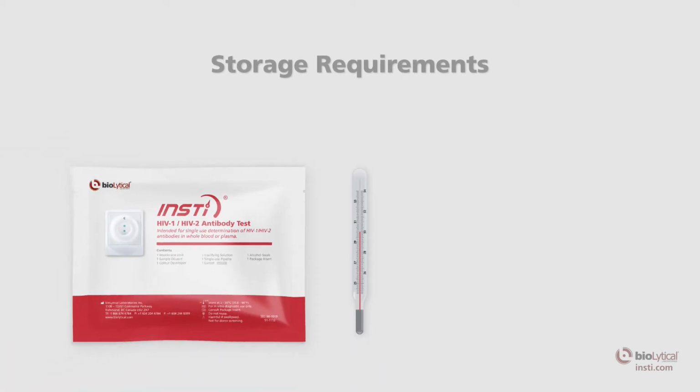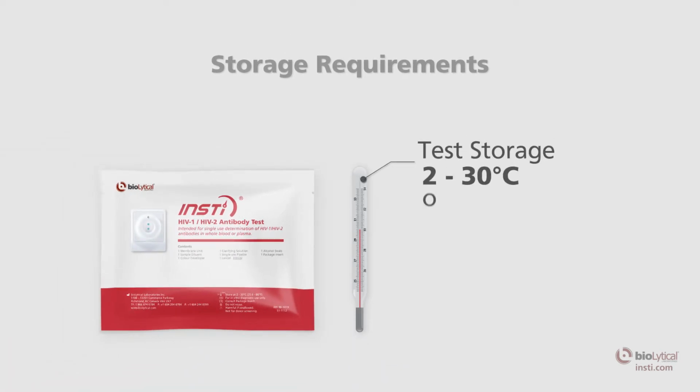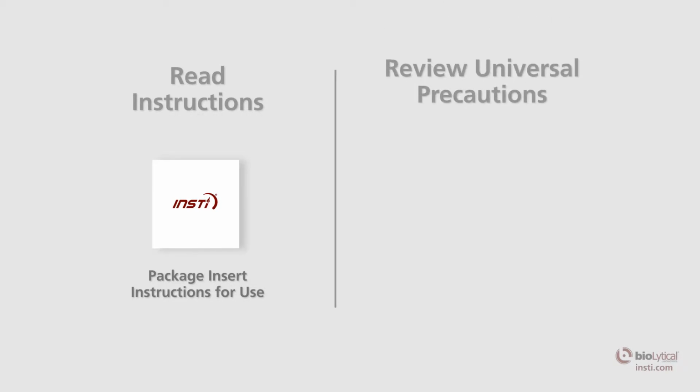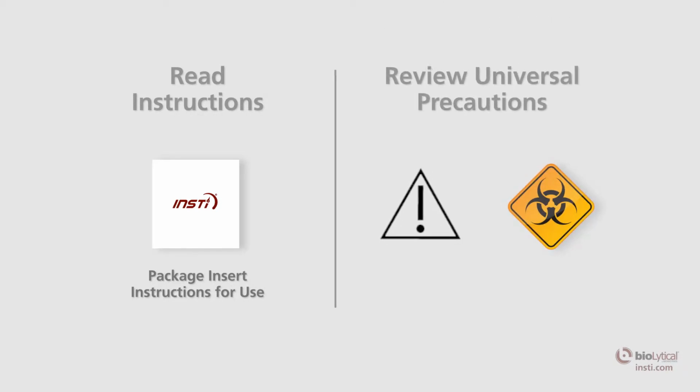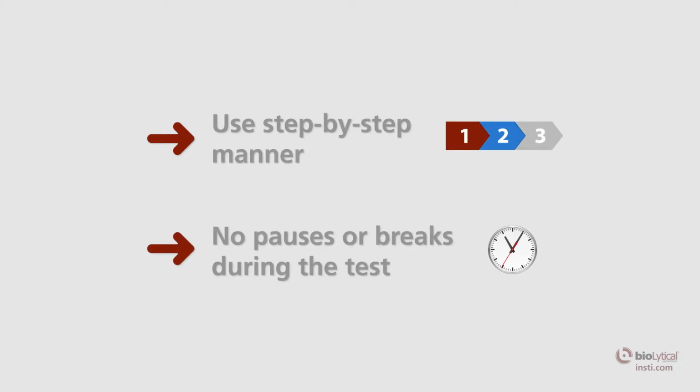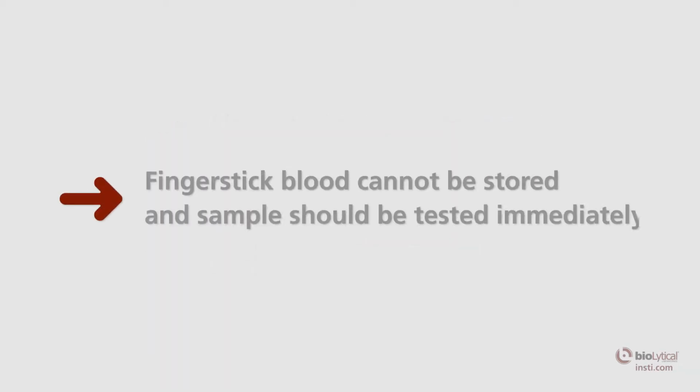The test must be stored at 2 to 30 degrees Celsius or 35.6 to 86 degrees Fahrenheit. Before using the test, read the package insert to familiarize yourself with INSTI and become familiar with universal precautions. INSTI is intended to be used in a step-by-step manner with no pauses or breaks during the testing process. Whole blood specimens collected by fingerstick should be tested immediately.